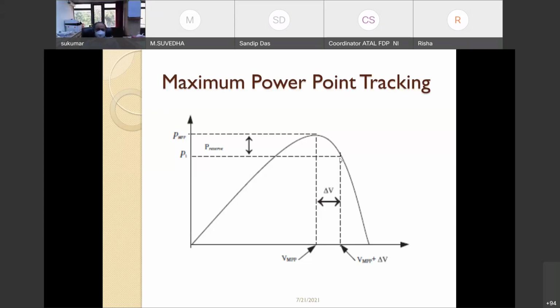And now at this point, you start providing a power which is proportional to frequency so that it can increase and decrease across this point. So this increase and decrease, if it is done with respect to df by dt, rate of change of frequency, then that extra power that is being produced apart from this operating point will be equivalent to inertial power that is coming from the rotating machine, because these are also very fast devices. Hence, the synthetic inertia can be produced from the inverter itself. Am I clear now?